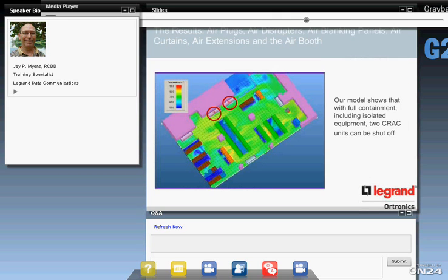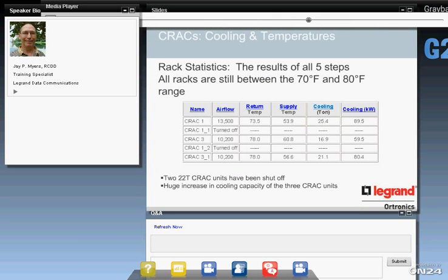Now, as a result of this, we can now turn off a second CRAC unit and still have all equipment be in acceptable range, temperature-wise. That's pretty dramatic savings there. And now, as you can see, the return temperatures are up quite a bit, and we've turned off a second CRAC unit. That's a big savings.